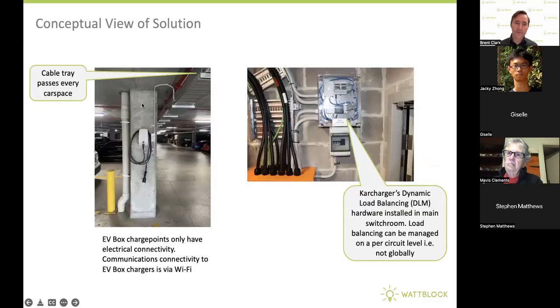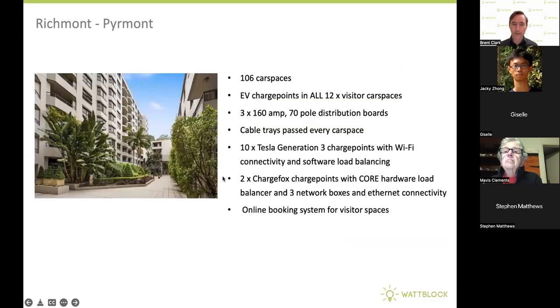So here's the cable tray running past the car spaces, with the EV box charger here. This is a load balancing system installed in the switch room, and it can do circuit level load balancing. For example, if you've got flat cables, that type of system could load balance clusters of vehicles on one flat cable. But in this particular building, they decided to use the cable tray rather than the flat cable.